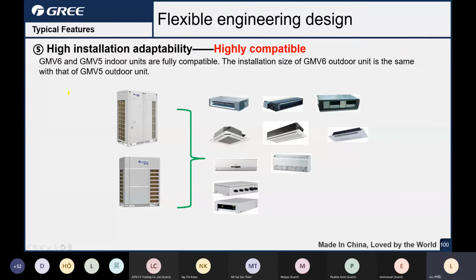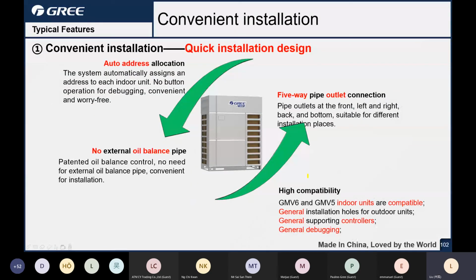And for the indoor units, it is compatible for GMV6 to use the GMV5 indoor units. The indoor units are the same. So if you have a lot of stock of GMV5 indoor units, no worry about them. This GMV6 can still use them. And for the installation, the addressing is automatic addressing, and the no oil balance pipe saves your cost of the copper pipe. And for the outlets, there are 5 directions: left, right, up and down, and the back, bottom. And the other compatibility is the same with GMV5. Indoor units the same. The debugging is almost the same.